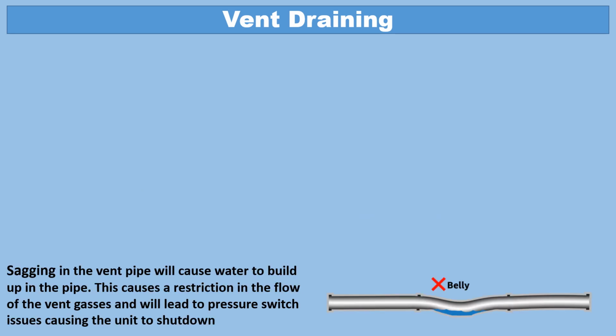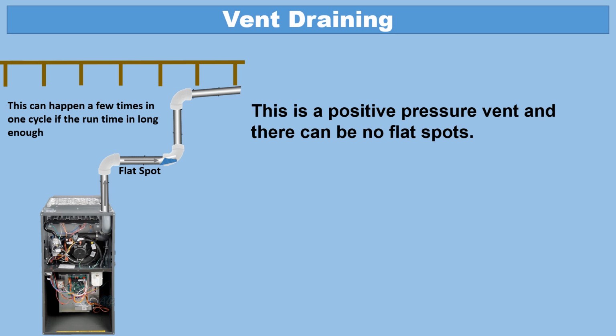Sagging in the vent pipe will cause water to build up in the pipe. This causes a restriction in the flow of the vent gases and will lead to pressure switch issues, causing the unit to shut down. This is a positive pressure vent, and there can be no flat spots. This building up of the water where that flat spot is, as you see on the left, this positive pressure vent is going to hold that water until there's too much water and it collapses. It causes a momentary flutter and it shuts the unit down.